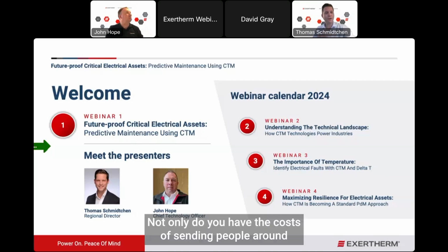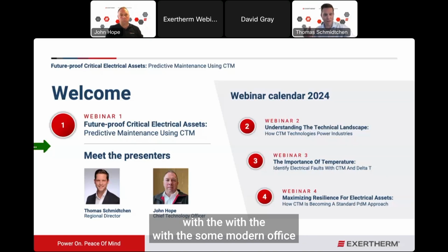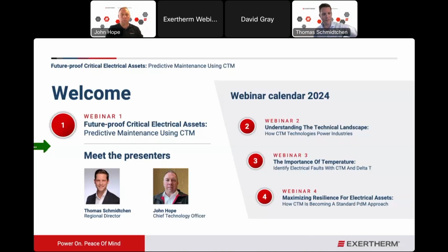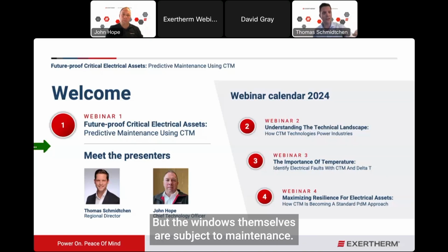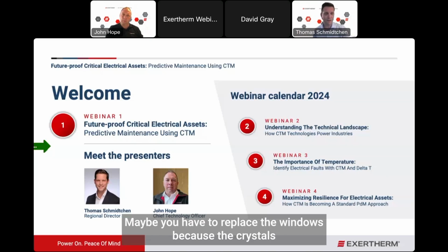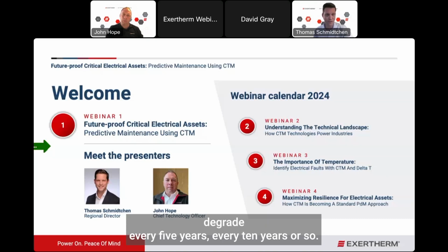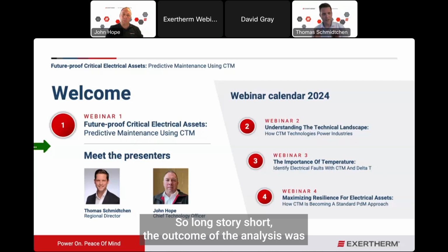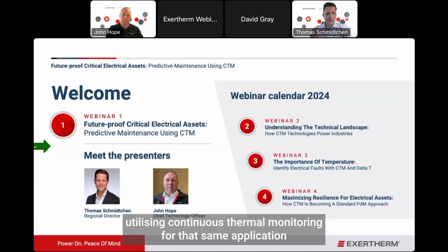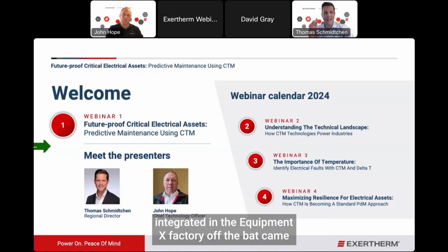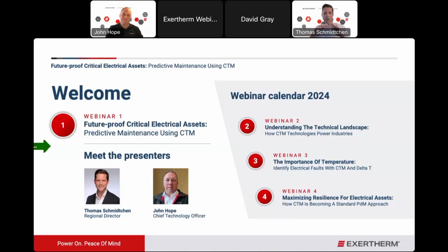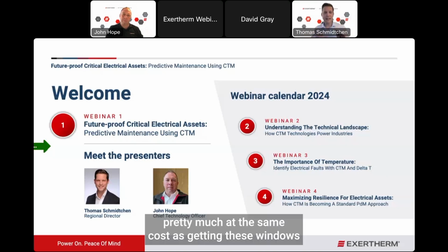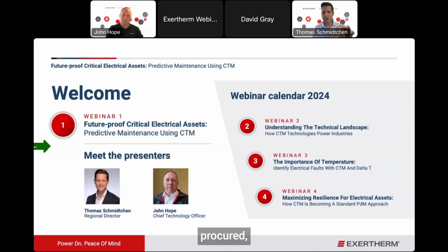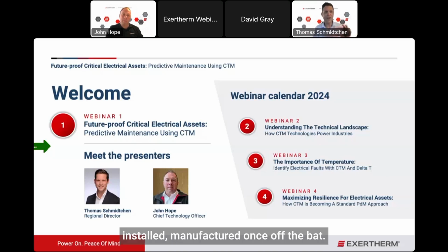Not only do you have the costs of sending people around with the thermographers and the cameras to look through those windows, but the windows themselves are subject to maintenance. Maybe you have to replace the windows because the crystals degrade every 5 years, every 10 years or so. So long story short, the outcome of the analysis was that utilizing continuous thermal monitoring for that same application, integrated in the equipment ex-factory off the bat, came pretty much at the same cost as getting these windows procured, installed, and manufactured once off the bat.